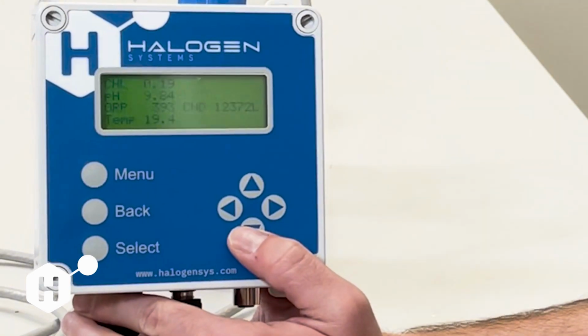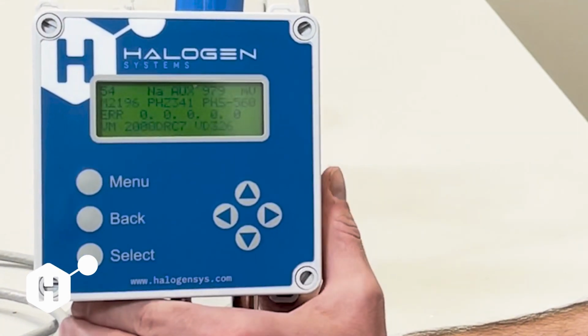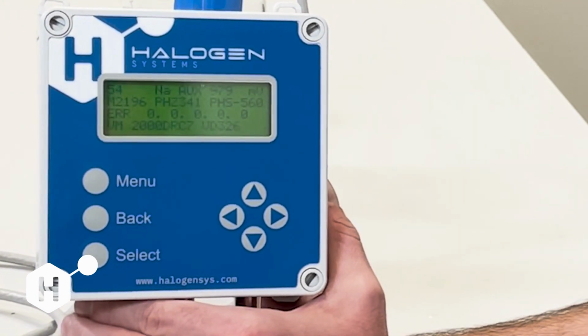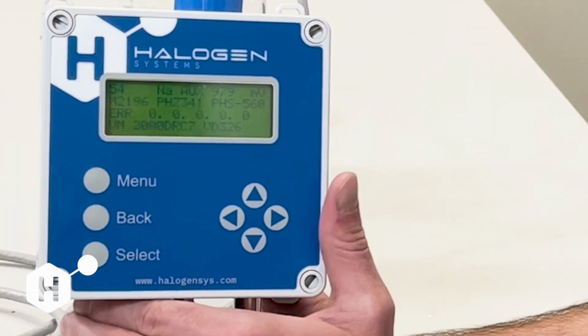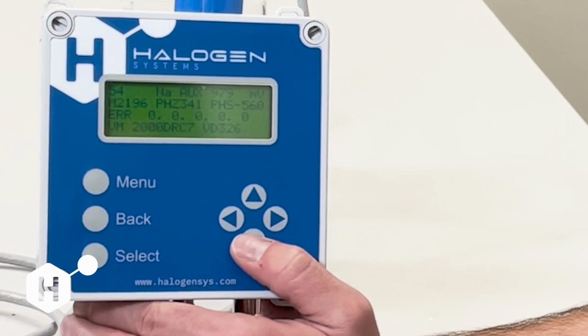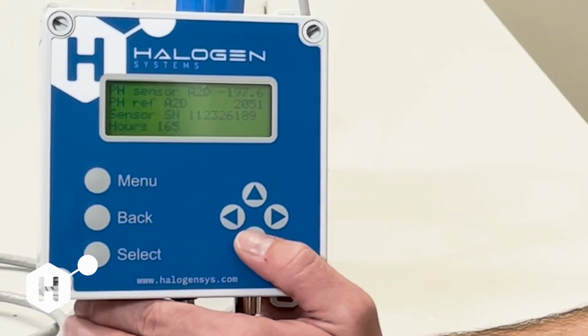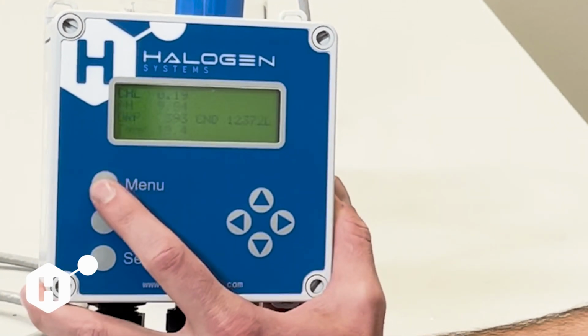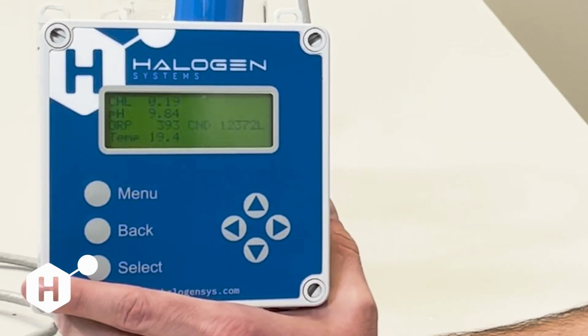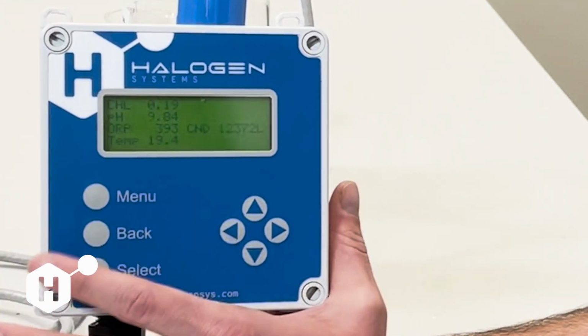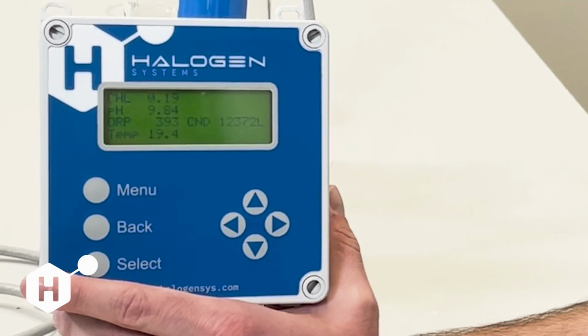And we're at pH 9.84. We come over here and there you go. Now our pH slope is updated to negative 56. So I know that I've had a successful pH calibration. We're at negative 197.6. And like I said, this value might go directly to 10 initially, but as soon as we start applying that temperature compensation, we might see a little bit of change.